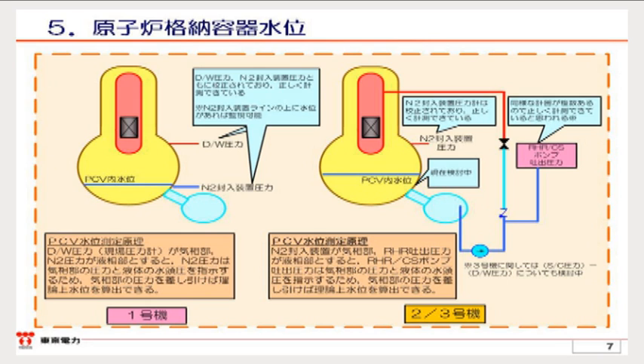In addition, Units 2 and 3 have similar measurement basics. They have pressure from the nitrogen supply apparatus as illustrated in red, and another one from the hydraulic head pressure of the suppression chambers, as the pumps in the residual heat removal system, whose discharge pressure indicator receives water from these suppression chambers, do not basically work currently. Therefore, we think we can also estimate the water levels of the primary containment vessels if we subtract the instrument reading of the discharge pressure of the pumps in the residual heat removal system from that of the nitrogen supply apparatus. We have slightly different approaches to each of the units, 1 to 3, but have been currently considering methods to theoretically calculate water levels in the primary containment vessels and will continue to work on this.